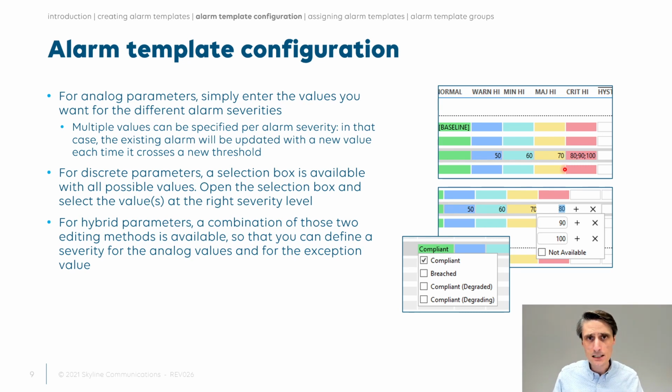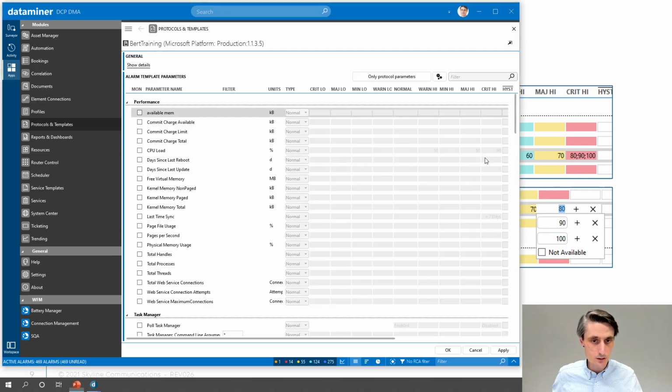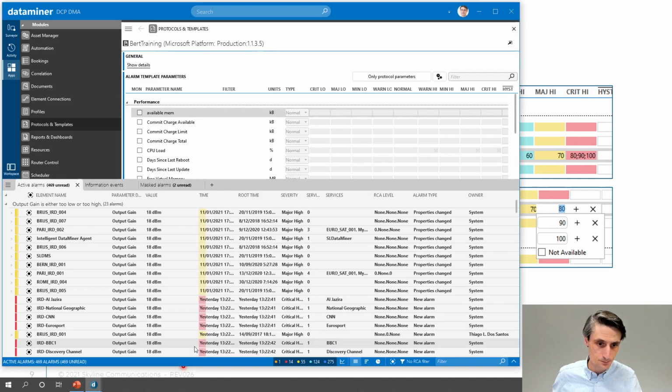Well, let's say that my value is continuously increasing. And it jumps, for instance, from 48, and the next polling cycle, it's 52. 52, whoa, we've reached that threshold here. So a warning high alarm will be generated. And the value, you can basically see it in the alarm console. There is a certain value specified here in the alarm. The value that is when the alarm was generated.